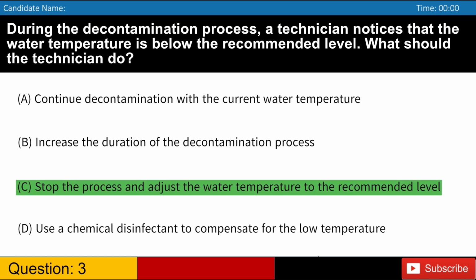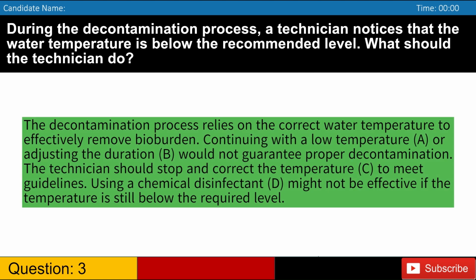Answer: C. The decontamination process relies on the correct water temperature to effectively remove bioburden. Continuing with a low temperature, A, or adjusting the duration, B, would not guarantee proper decontamination. The technician should stop and correct the temperature, C, to meet guidelines. Using a chemical disinfectant, D, might not be effective if the temperature is still below the required level.